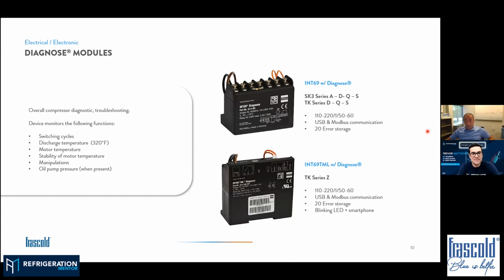This is how the protection module looks. They are different for what we have discussed, because on the Z compressor, our largest compressor, we have an oil pump. Therefore the second module below is capable of controlling all the oil pump parameters. But both of them are capable of recording and controlling the number of switching cycles.